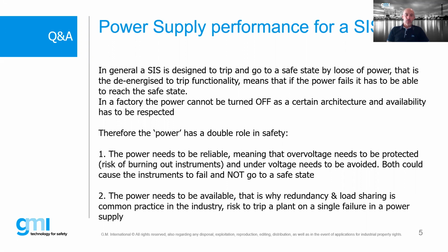So the overvoltage protection has to protect your instrumentation. We had this experience: in the switching power supply we have a 400 voltage inside, which is a typical circuit inside switching power supplies. And we have experienced that this 400 voltage went directly to the loads, and this burned the systems completely. This is a really unwanted situation. But if you use a system with an overvoltage protection outside, this will be protected. And over 30 volts will be a dangerous failure and it will be stopped completely.